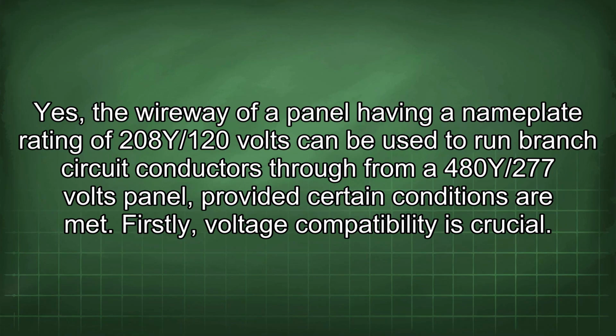Yes, the wireway of a panel having a nameplate rating of 208Y/120 volts can be used to run branch circuit conductors through from a 480Y/277 volts panel, provided certain conditions are met.